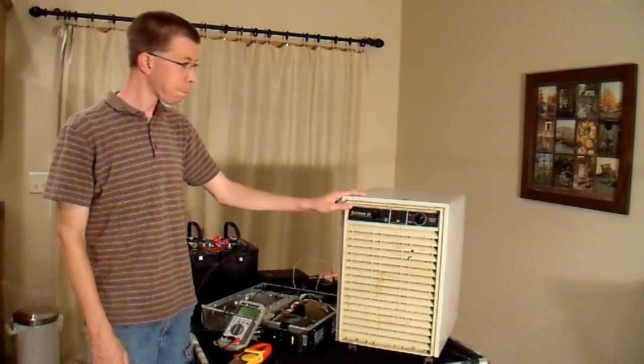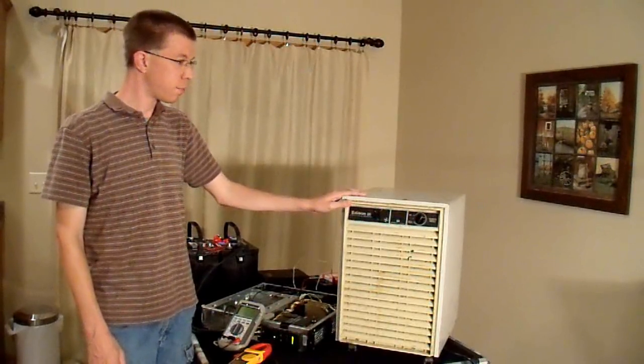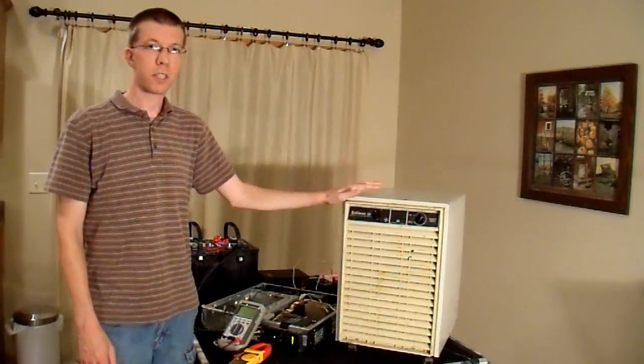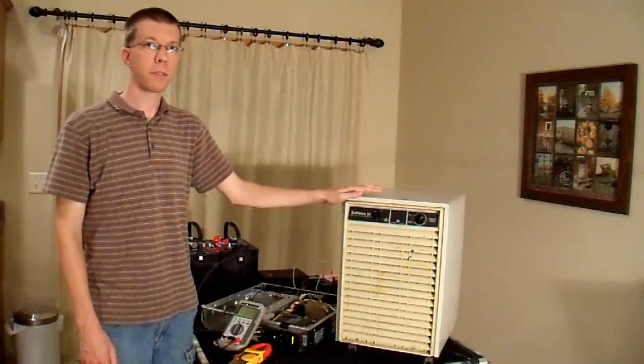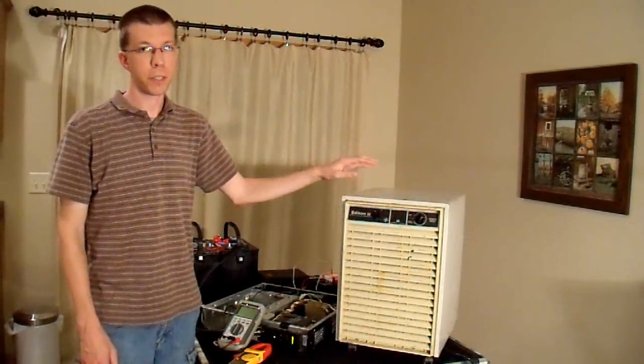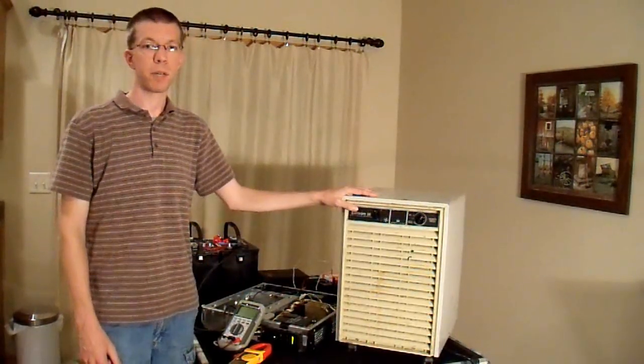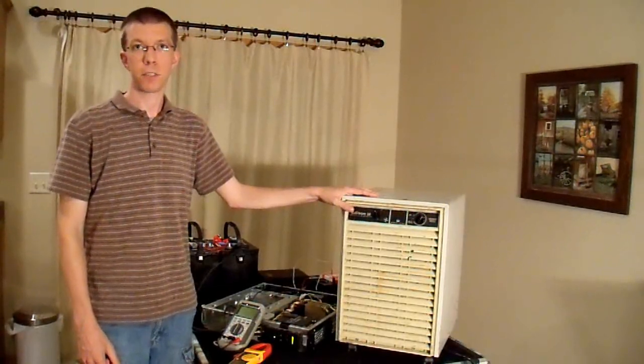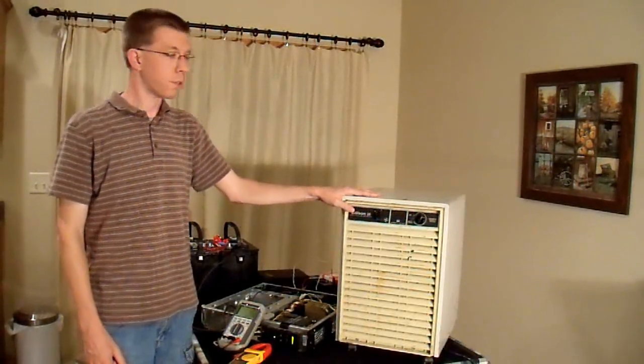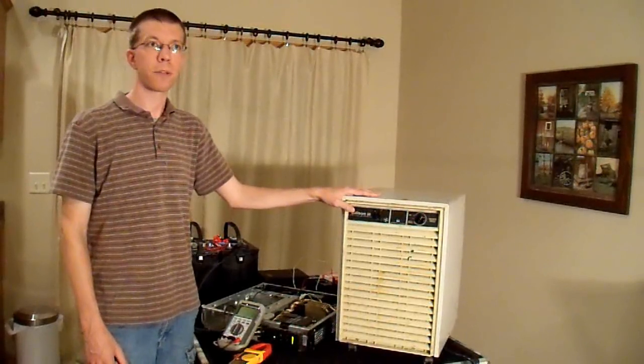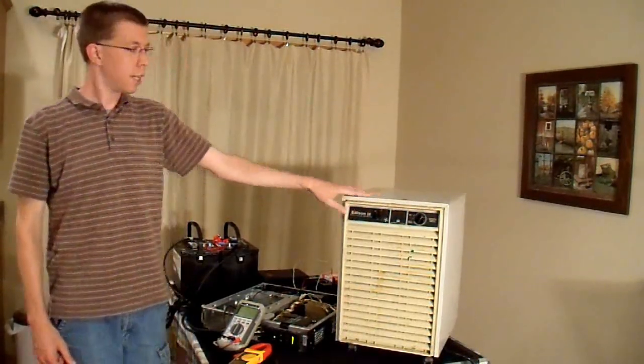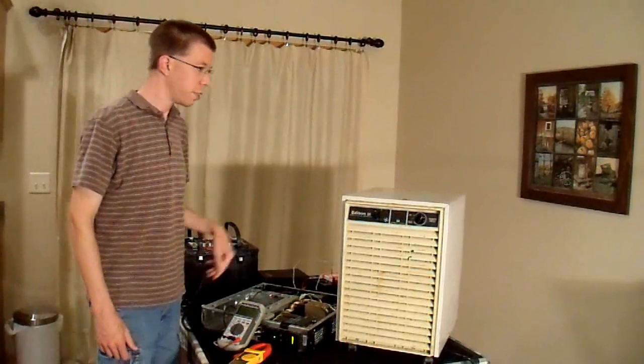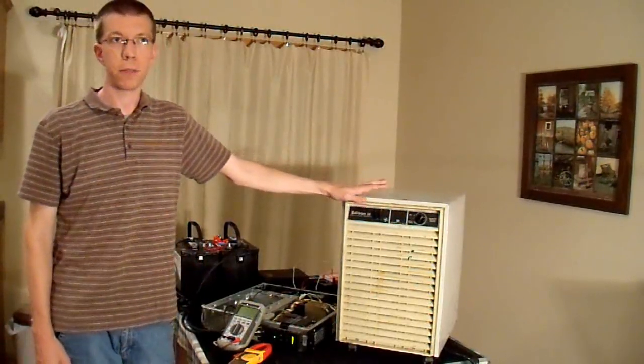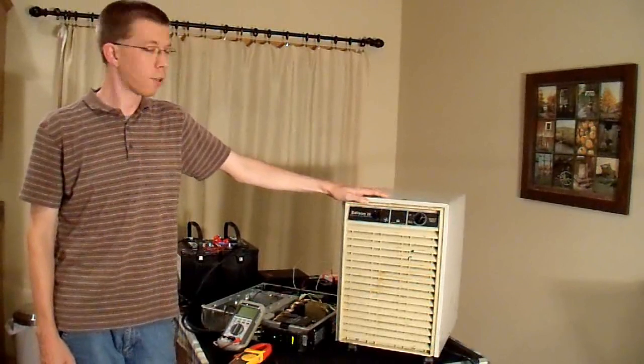But one thing that's nice about it for this application is that once you start the pump, the pressure differentials inside the unit build, and if it gets shut off and restarted without letting those pressure differentials even out again, it's actually incapable of turning the pump over. It just doesn't have enough starting torque, the motor inside. So I can pretty easily get a locked rotor current draw measurement out of this unit, and it'll be much higher than what it operates at normally.